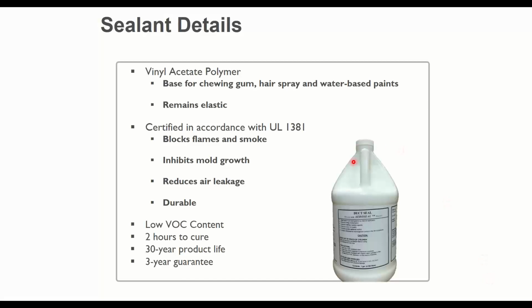The product life, just sitting in a jug on a shelf, is like a two-year life because it starts settling out. But once you turn it into an aerosol and mix it with compressed air and put it into the duct system, at that point, you then have a 30-year life expectancy on the material. And you also get, commercially, a three-year guarantee on that. So if you have any duct leakage that shows up in the first 3 years, then somebody is going to be coming back out there to seal it back up for you. Once again, not me, somebody else.